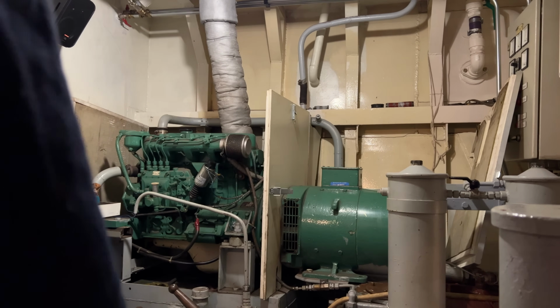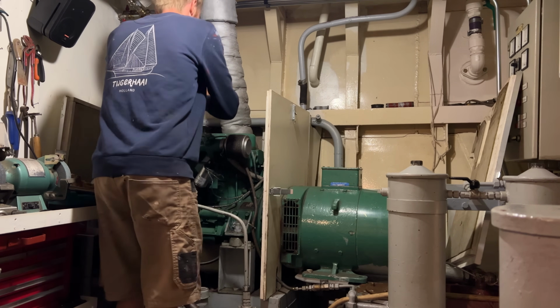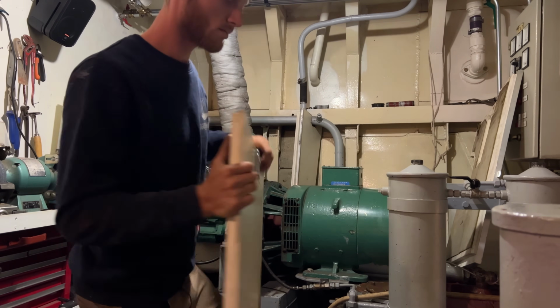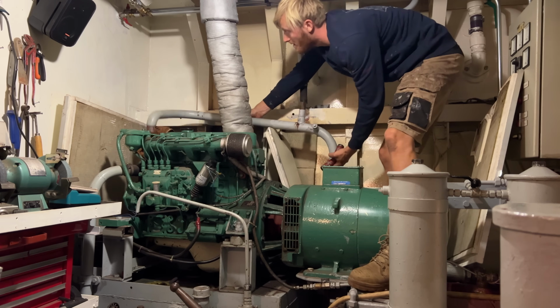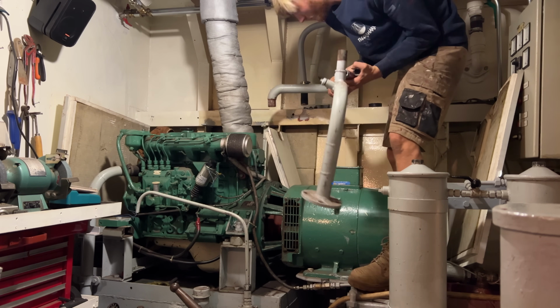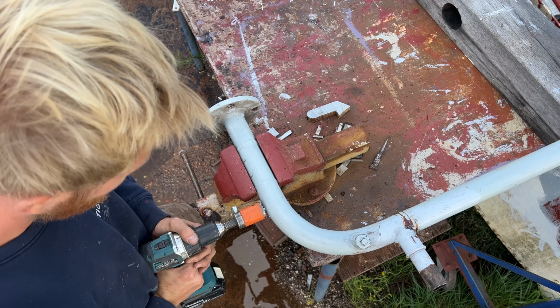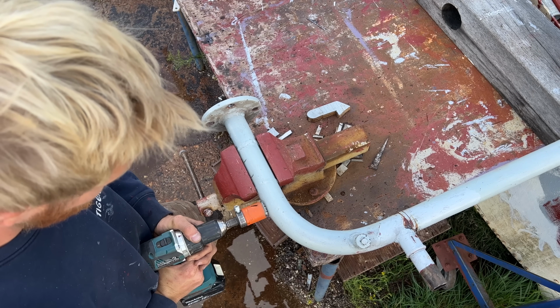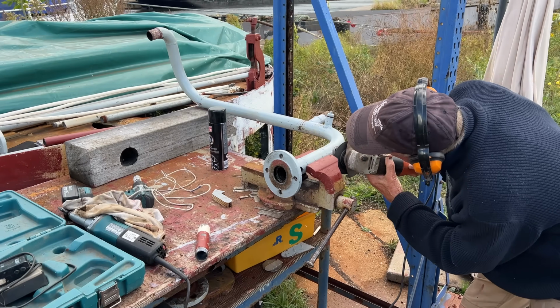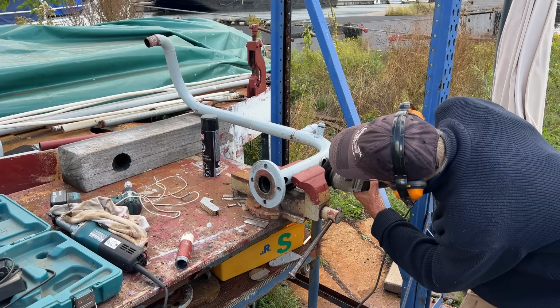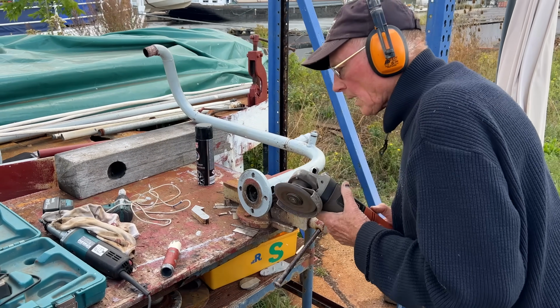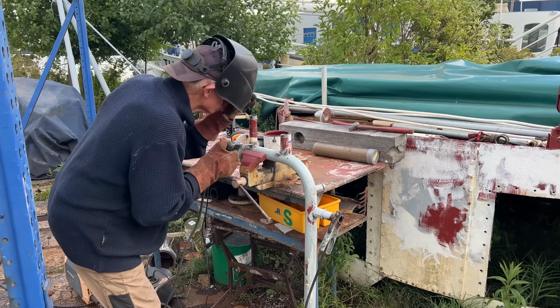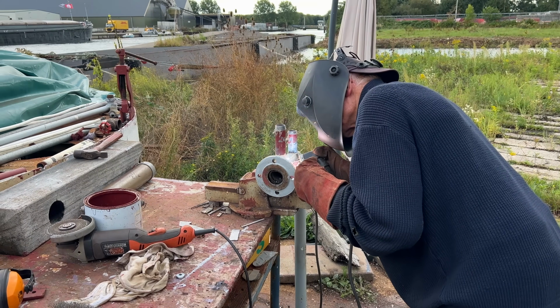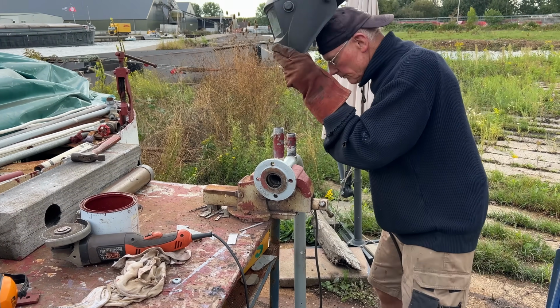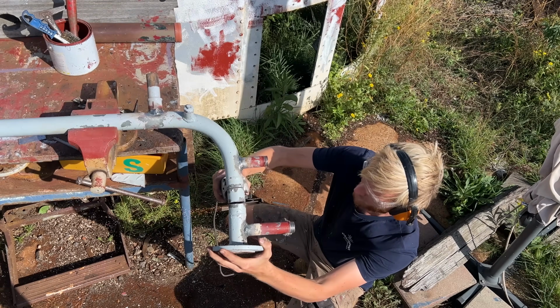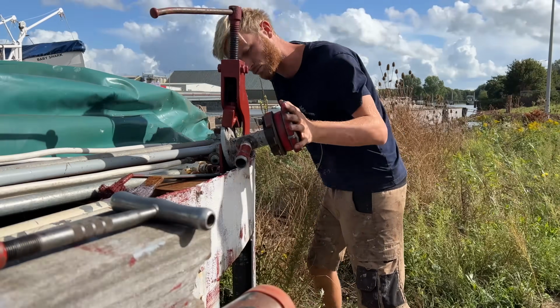To use the engine coolant, we do need to make some adjustments to our piping, starting with the large generator. The hotline needs 2 branches, one towards and one return from the buffer tank. To make sure the water actually flows through the heat exchanger coil, we're installing a gate valve between the 2 branches.